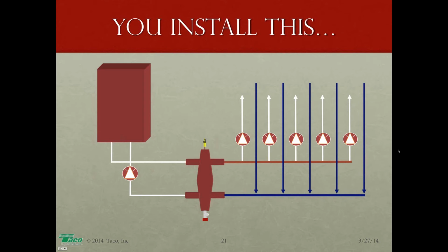Steve Jansen says, would it make sense to match the lowest boiler output to the minimum zone heat load? If you can. Again, it depends on the boiler. What you're talking about there, Steve, is we're going to get right into that on the minimum boiler, the lowest boiler output, and the minimum load zone. If one's bigger than the other, one's smaller than the other, how do we deal with it? What you're talking about is we're going to be making a case for buffer tanks in about 2 minutes. So good question. I'm glad you asked that. Okay. Very good.